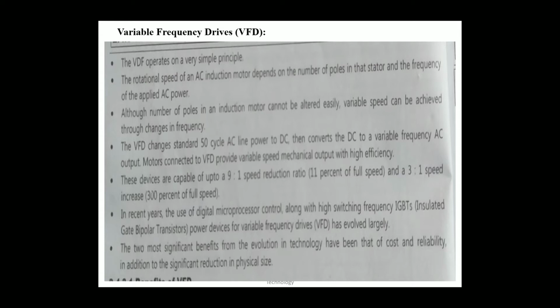Although the number of poles in an induction motor cannot be altered easily, variable speed can be achieved through changes in frequency. The VFD changes standard 50 cycle AC line power to DC, then converts the DC to a variable frequency AC output. The motor connected to the VFD provides variable speed mechanical output with high efficiency. These devices are capable of up to a 9:1 speed reduction ratio, that is 11% of full speed, and a 3:1 speed increase, that is 300% of full speed.